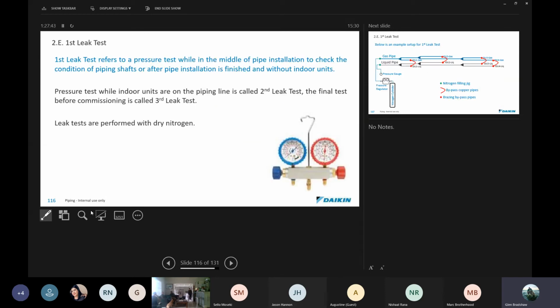So the first pressure test refers to a pressure test in the middle of piping installation, to check the condition of pipe shafts, and after pipe installation is finished and without indoor units. The pressure test while indoor units are on the piping line is called the second leak test, and the final pressure test before commissioning is called the third leak test.